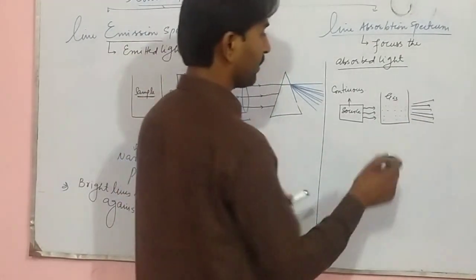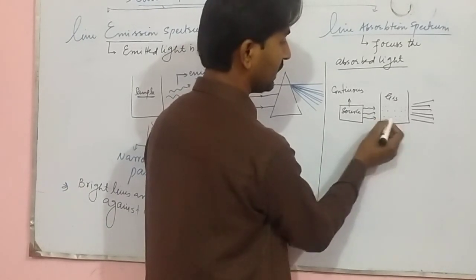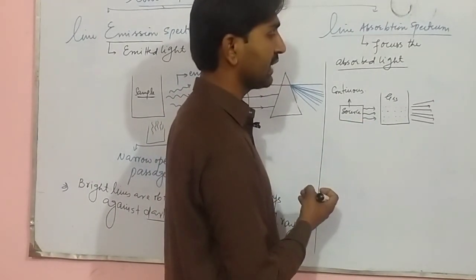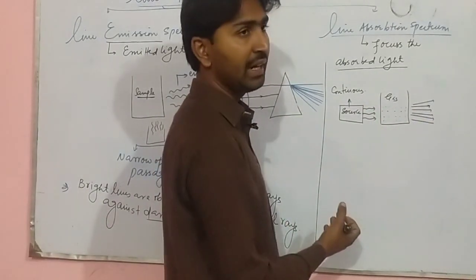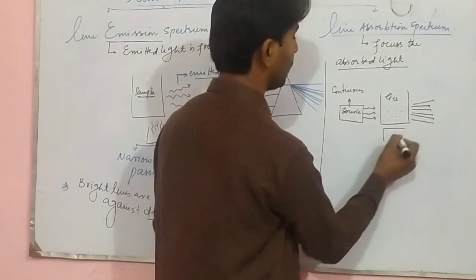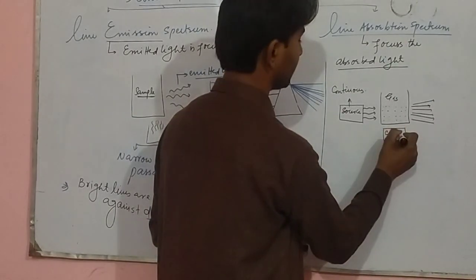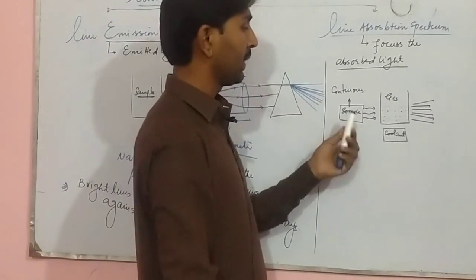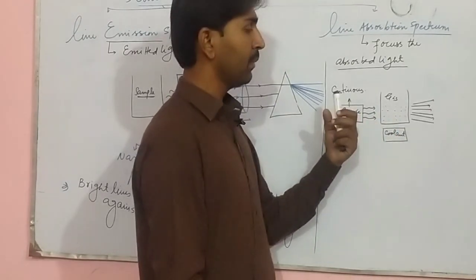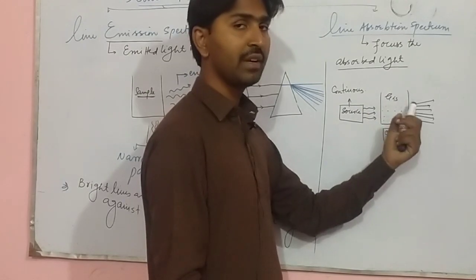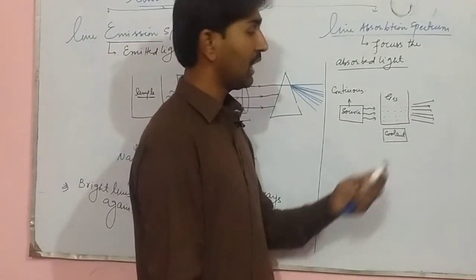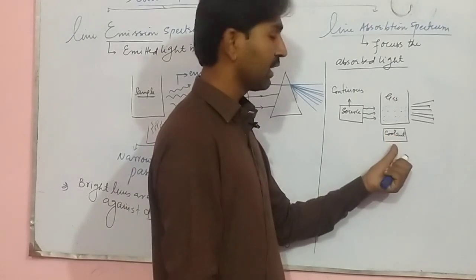In this situation, when the gas absorbs the light, it may get excited, and after exciting, it may give out the light. To prevent this, we must have a coolant system. By absorbing the light from the source, the gas may heat up, and by heating it may emit the same radiations which were absorbed. So to prevent heating or emission of light, we use a coolant system.